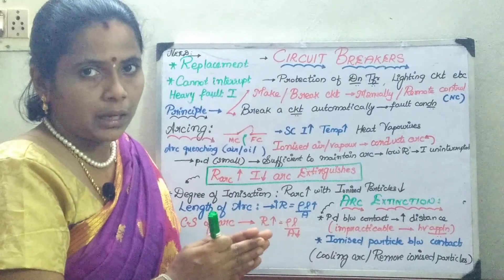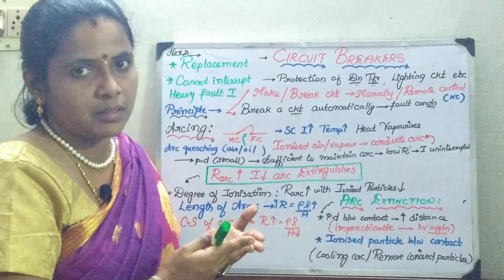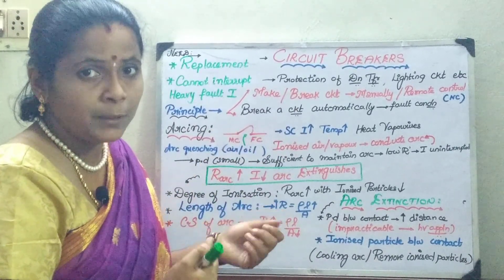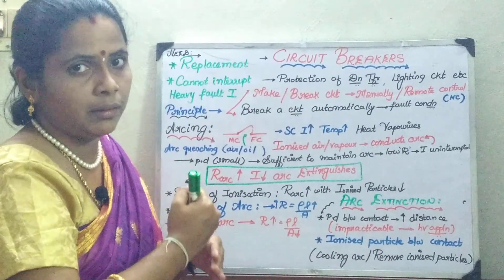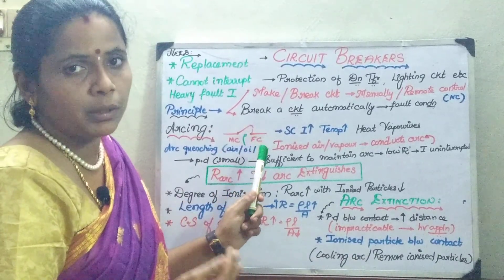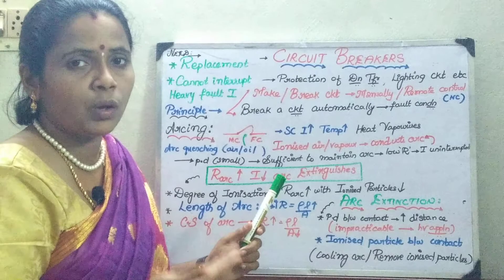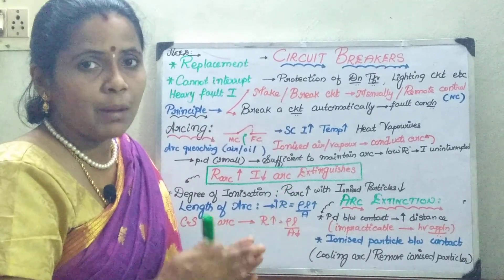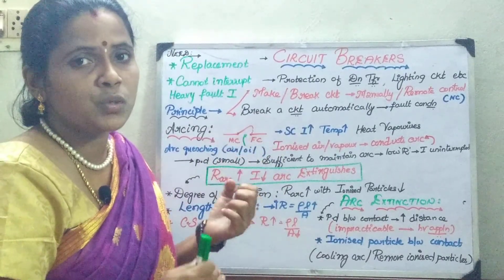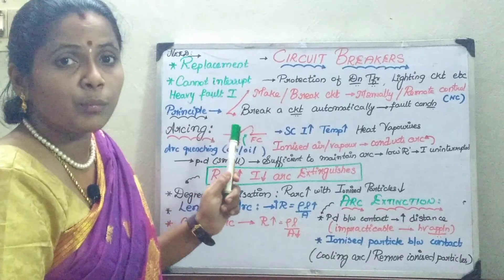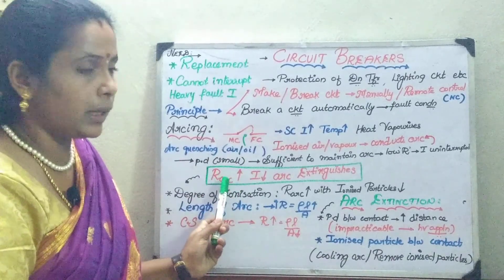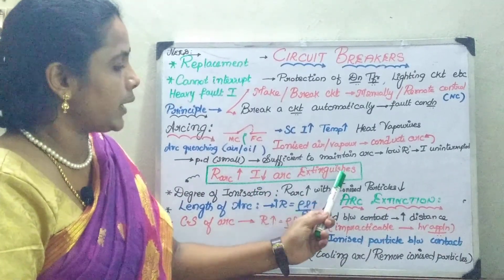We must find some mechanism to increase the arc resistance. In other words, we try to remove the ionized particles from the path, or increase the arc resistance so that the arc gets quenched. A lot of arc quenching medium must flow — it can be either oil, air, SF6, vacuum, or air blast. It is an utmost necessity that the arcing products be removed so that the fixed contact remains apart from the moving contact. We will see the mechanisms by which we can increase the arc resistance so that the current decreases and the arc extinguishes.